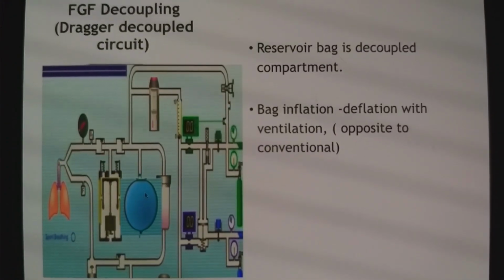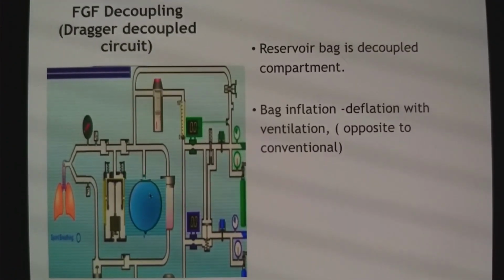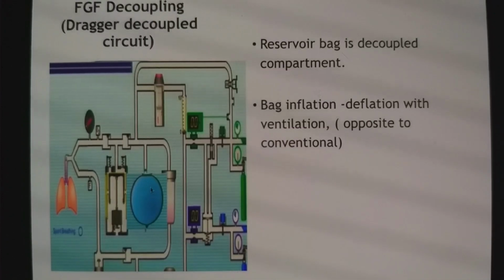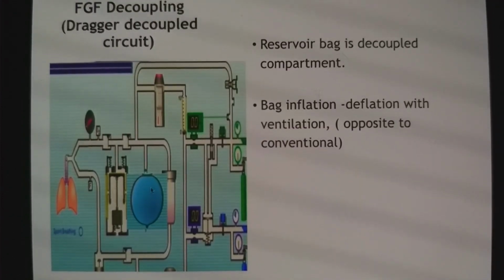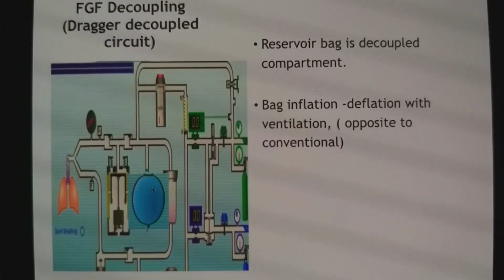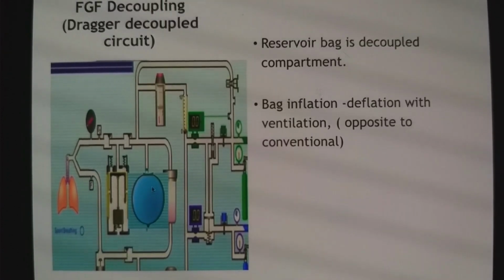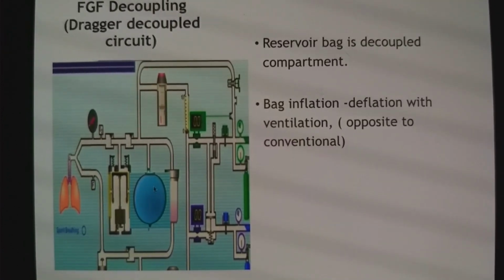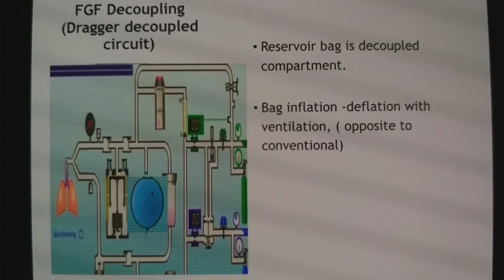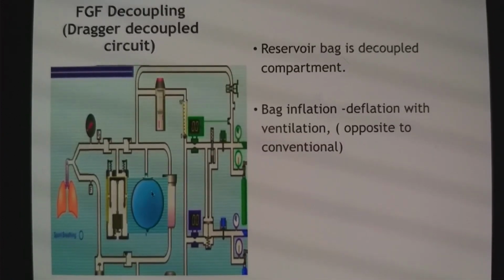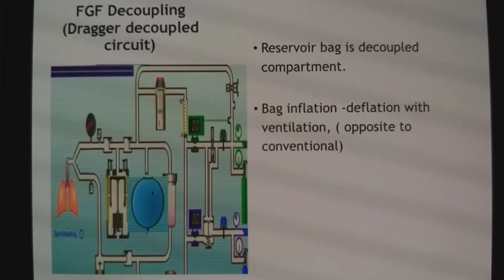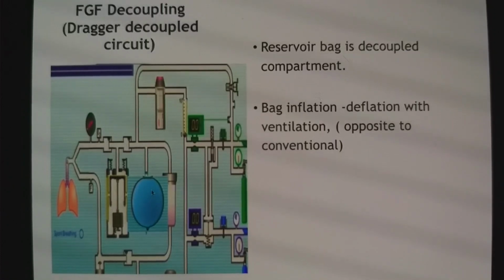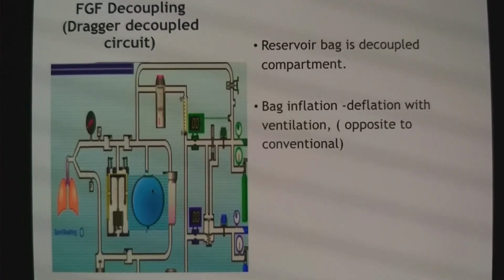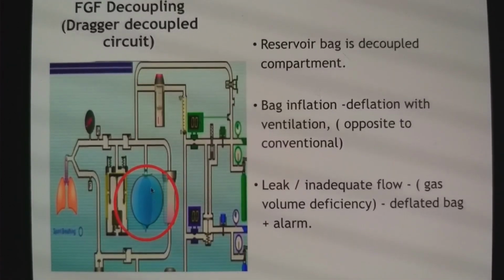Now we are always used to a situation where when you squeeze the bag, inspiration occurs. So in inspiration, bag is collapsing, and in expiration, bag is inflating. That is our routine understanding. But when you see these Draeger machines with decoupled technology, the bag inflation is opposite. During inspiration, because of decoupling valve, the bag gets expanded and it gets collapsed during expiration. So it is opposite to your conventional thinking.